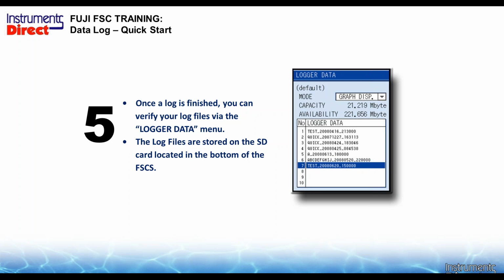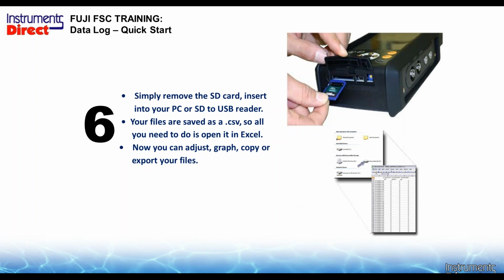Once your log is finished, you can verify your logs by looking at the logger data menu. You'll see the names of the logs that you put in, and if it was a quick log, it'll say quick in front of it. All these files are stored on the SD card, which is at the bottom of the flow meter that we provide with the meter purchase or rental. And as I said, it's stored as a CSV file. The next step is you want to get the data out. We have two ways. You can plug in a USB cable, which will take a while to get the data out, or just pop out the SD card. If you don't have an SD port in your laptop or PC, guess what? We give you a USB reader right along with it.